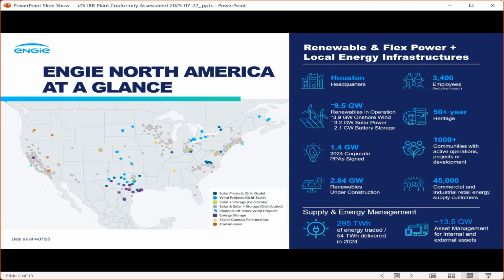What do I do in this very large company? I work in the operations engineering department, which means we work primarily on assets that are past COD. We have, I think, an interesting perspective on conformity assessment and compliance, because we look at it in a backwards looking way, since we're introduced to these things when operational problems with IBR plants occur in the field. Generally, my team isn't working on studies happening during the design phase or interconnection phase of plants. However, whenever an IBR facility we own or operate has an actual operational performance issue, or an apparent failure to perform or meet interconnection requirements, we're the people who start digging into why that happened. That's where we gain an interesting perspective on what studies have or haven't been done during the design or commissioning phase of the project.